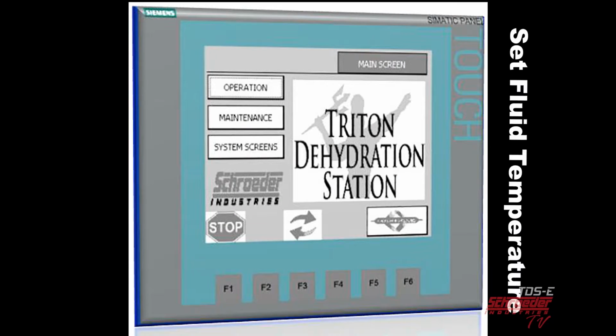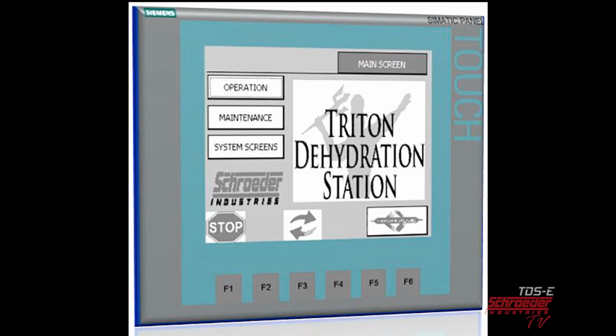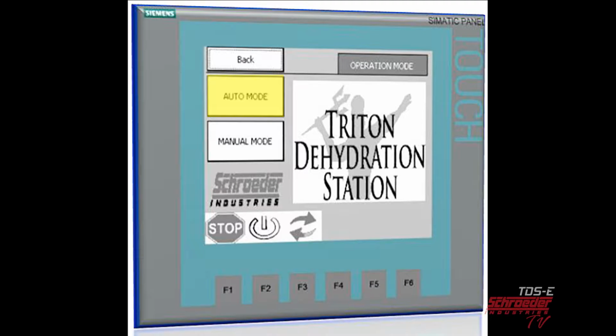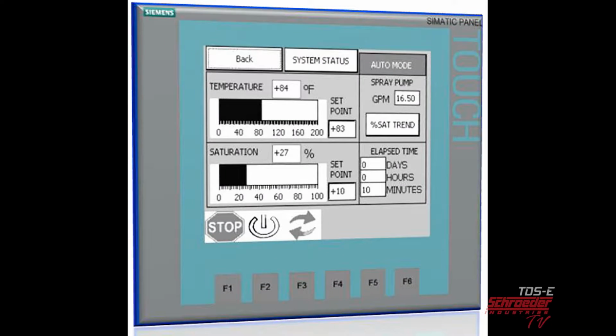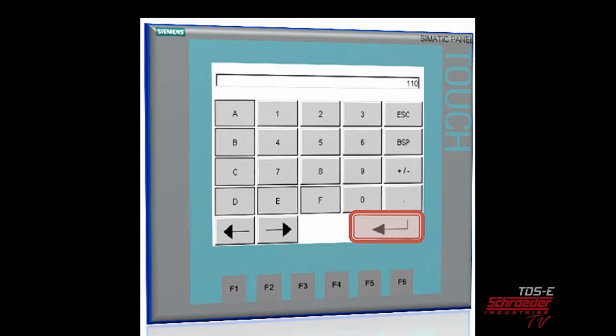Set the fluid temperature by following these steps through the touch panel. Click on Operation in the main screen. Click on Auto Mode on the Operation Function screen. Click on the I/O field shown as plus 83 below set point in the temperature section on the Triton automatic mode screen. The following keypad will display. Type the desired temperature followed by Enter. Note, the maximum allowed temperature is 135 degrees Fahrenheit.